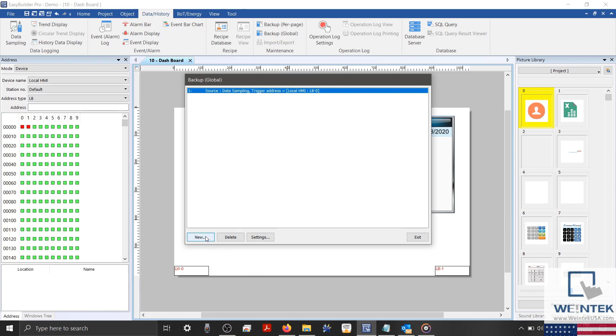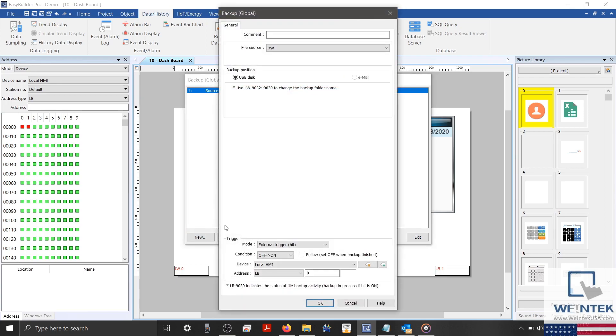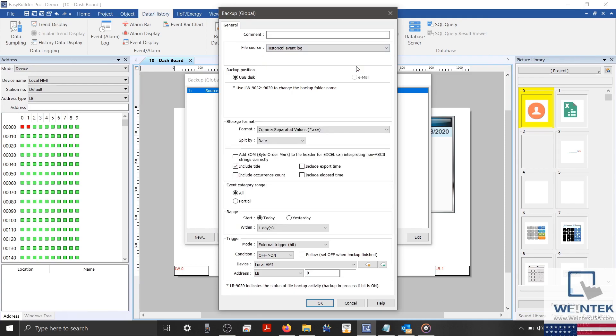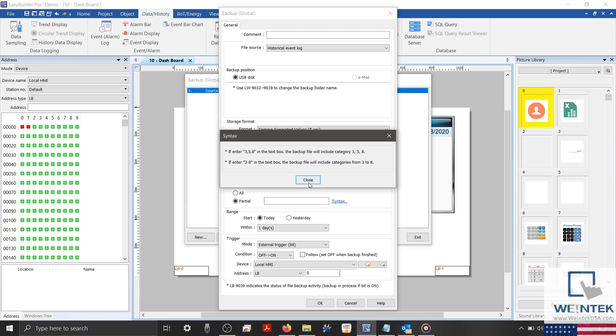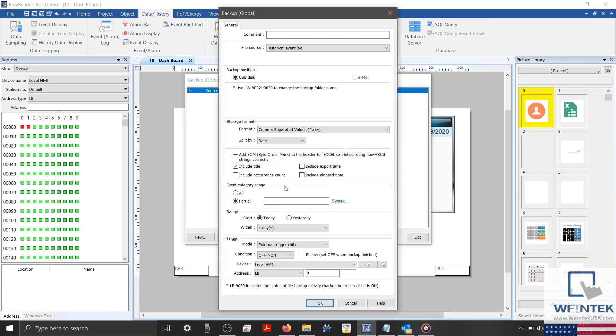Now, I'll create one more backup object. Within this object, we'll set our File Source to Historical Event Log, and towards the center, you'll notice that we have a few additional settings. These additional options will allow you to include the export date or alarm statistics like occurrence count and elapsed time within the CSV file. Alarms are assigned to a specific category, which is category 0 by default. Here we can specify event categories that we wish to export using the specialized syntax, or we can export all categories, which is the default setting.